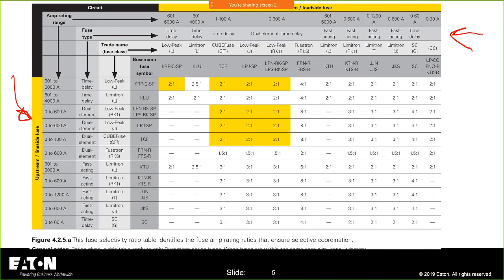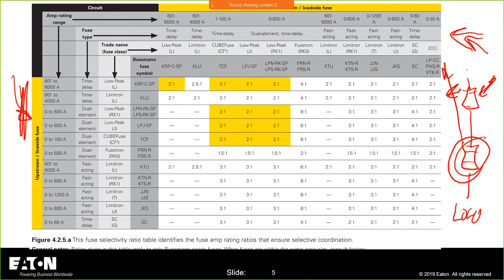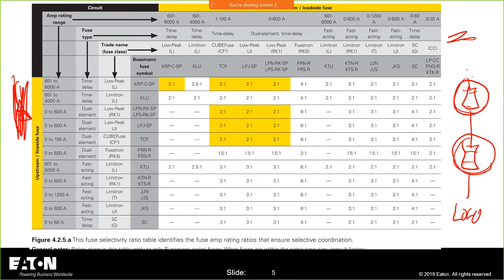So in a system, when I say downstream and upstream, I have a fuse feeding a fuse, and say this is the load. That fuse is down here on this side. This fuse is up top. Now, if I've completely confused you, then I've done my job. So the downstream fuse is across the top. The upstream fuse is down the side. So what you would do for any one of these, if you'll notice the 2-to-1 ratios on the LPJs, on the TCFs, on the LPN and the LPSs, these are 2-to-1 ratios.